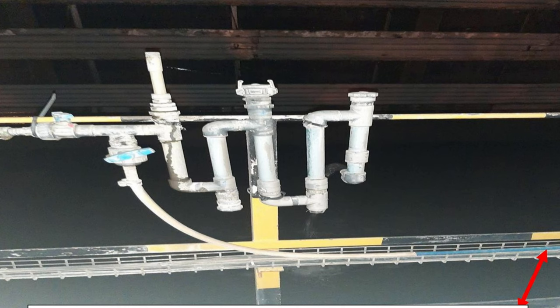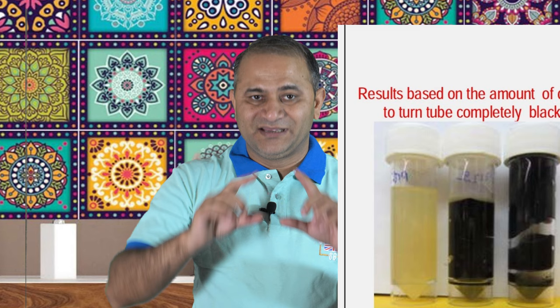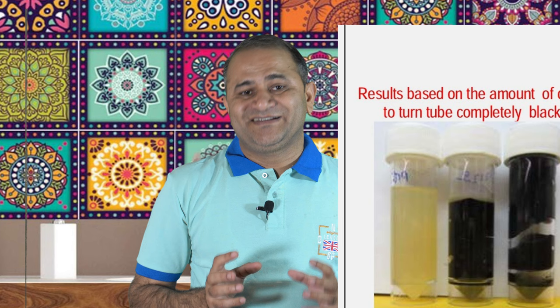If our cooling water system doesn't have a saline measuring unit, another method is to make a biocell. The best method is to add a 12 mm PVC pipe in our system and allow cooling water to flow through that pipe constantly. We then cut that 12 mm PVC pipe and clean its outer surface with ethanol. Ethanol will remove sulfate-reducing bacteria from the outer surface due to its disinfecting properties. We then put these samples in Sani-check agar and monitor the results. Sani-check agar will show the presence of sessile SRB, and you can compare results with the chart provided by Sani-check.